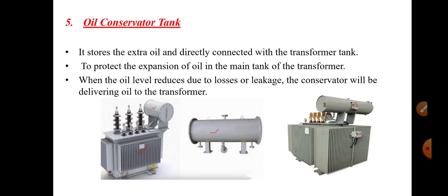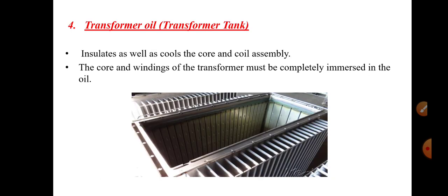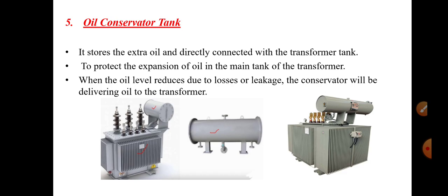The oil conservator tank plays a very important role in the transformer. It is cylindrical in shape and is connected to the transformer tank. Sometimes the oil level reduces in the transformer tank due to leakage or losses; at that time the conservator tank delivers oil to the transformer, acting as a reservoir. It stores extra oil and is directly connected to the transformer tank. The main purpose of this tank is to protect against the expansion of oil in the main tank.